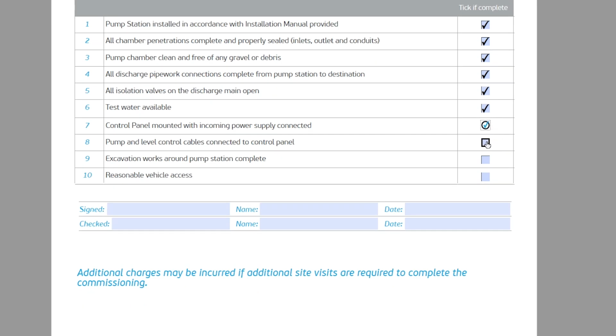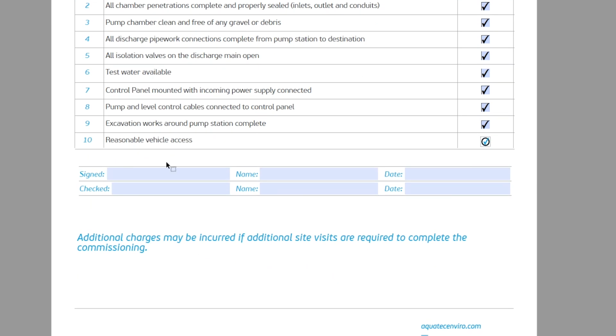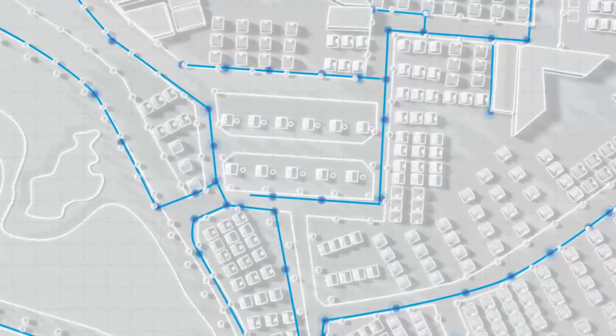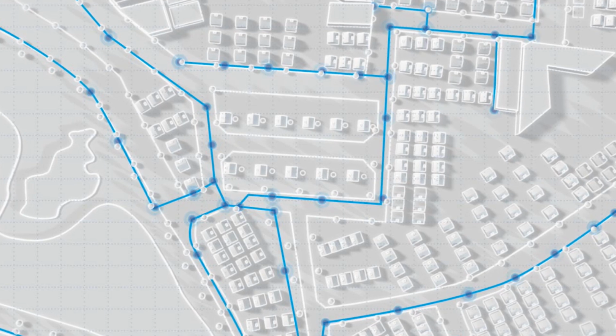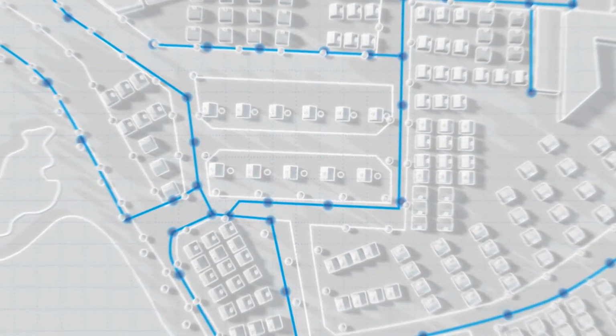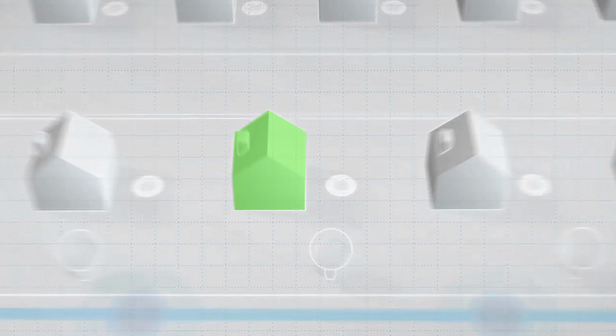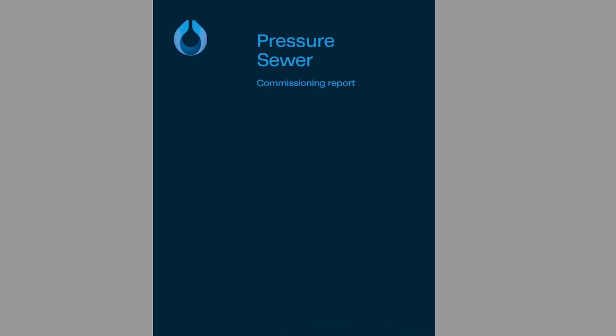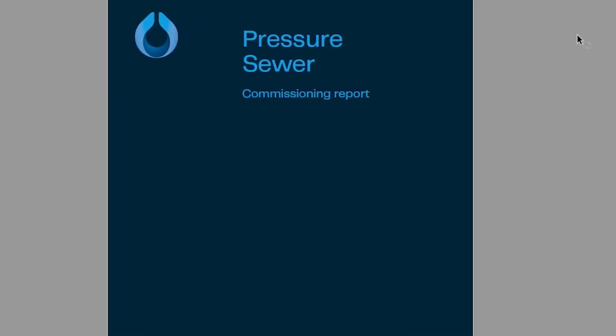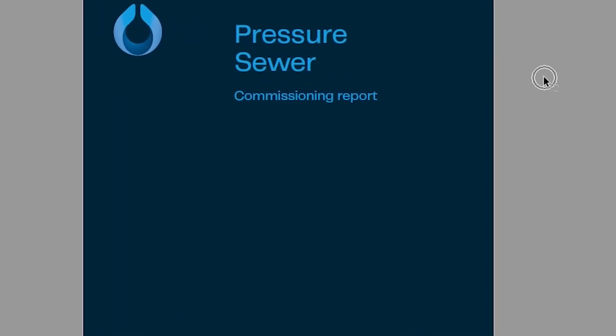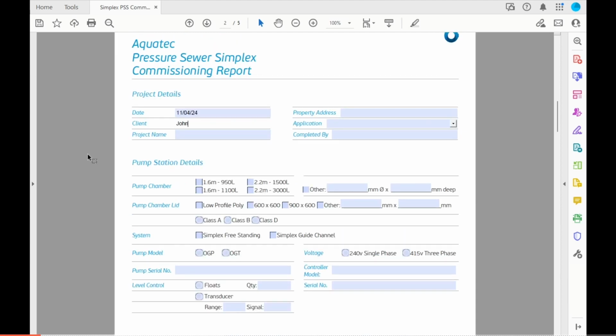It's important the commissioning documents are completed accurately, as they may be referred to in cases of equipment damage, system upgrade, or component replacement in the years ahead. Ensure site-related information is completed accurately, as there may be multiple stations on the one site, which will need clear differentiation to identify each particular station for future reference. Once confirmed that all pre-commissioning requirements have been met, we can begin with the project-specific commissioning report.